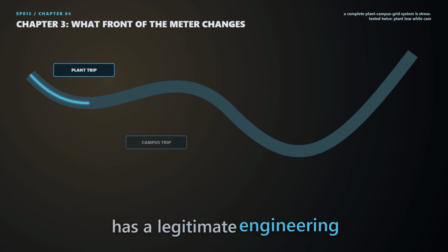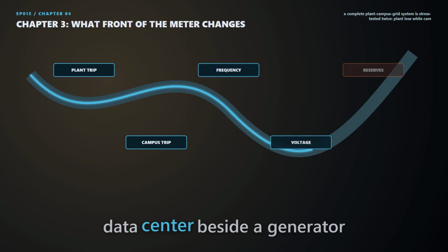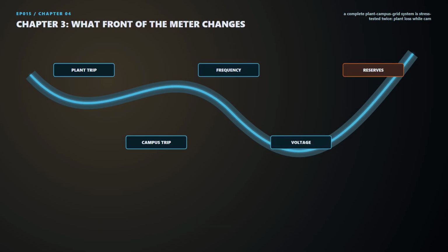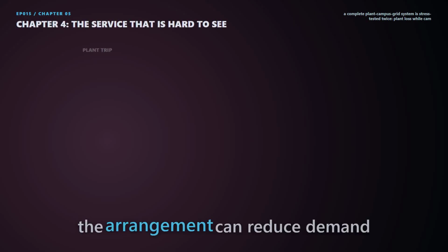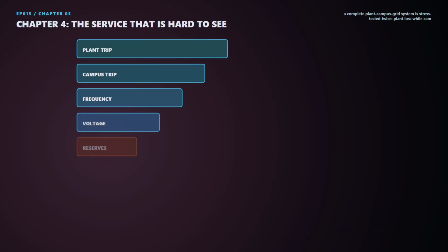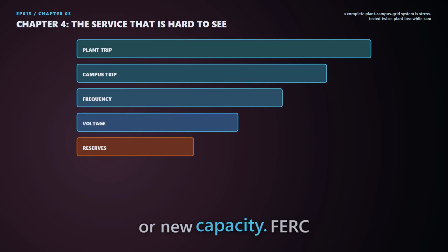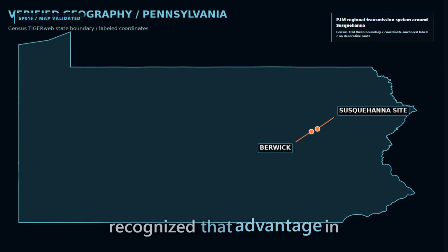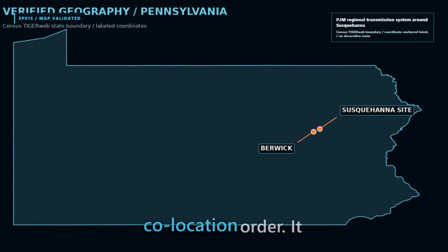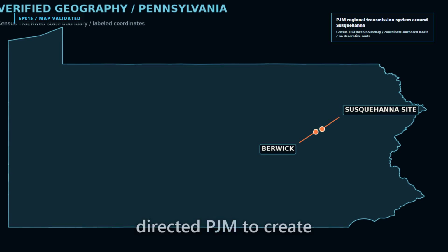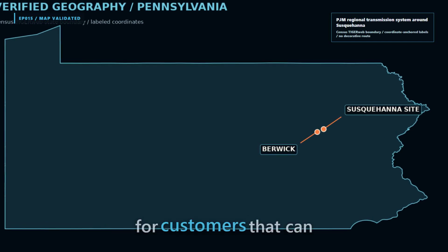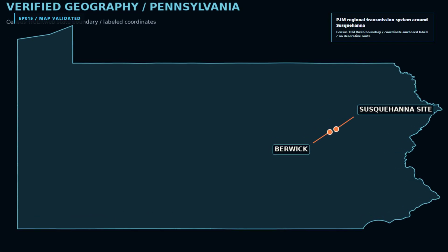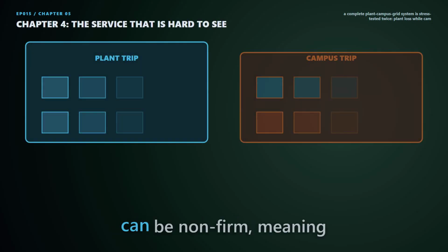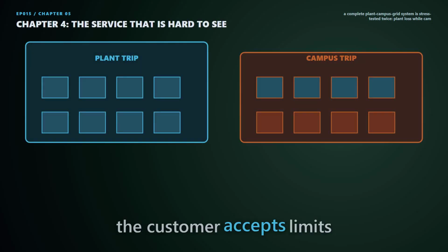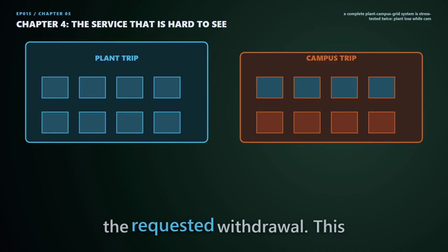Co-location has a legitimate engineering advantage. A controllable data center beside a generator can limit how much it withdraws from the regional grid. If the arrangement can reduce demand during stress, PJM may avoid some network upgrades or new capacity. FERC recognized that advantage in its December 2025 co-location order. It directed PJM to create clearer transmission options for customers that can control their withdrawals. One option can be firm. Another can be non-firm, meaning the customer accepts limits when the system cannot support the requested withdrawal.